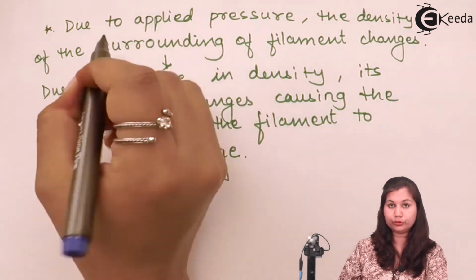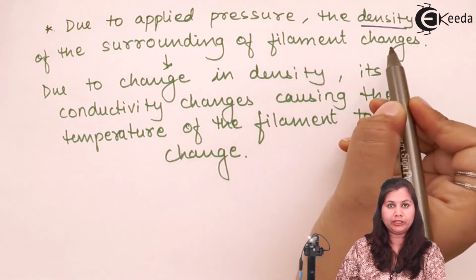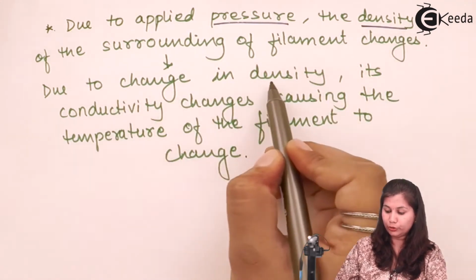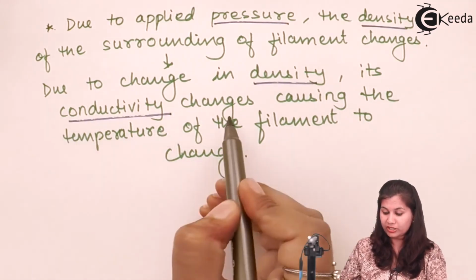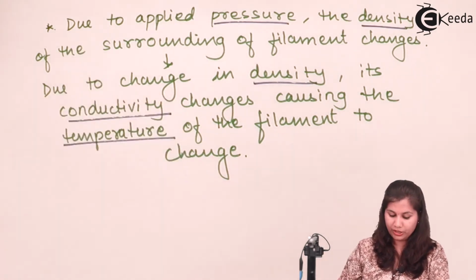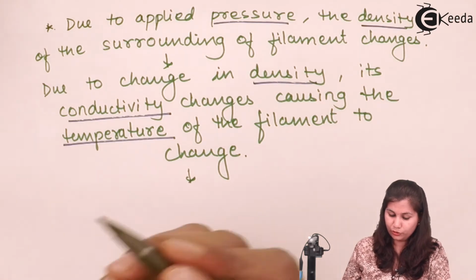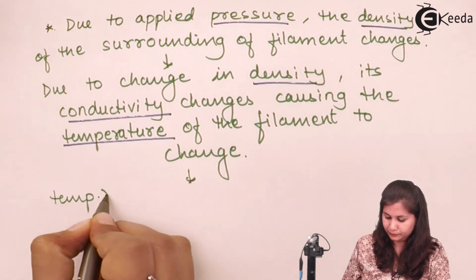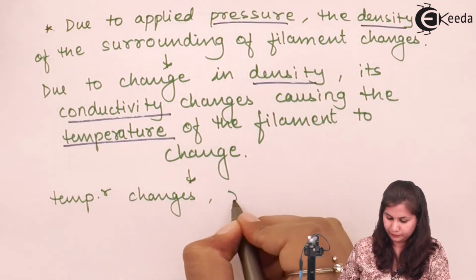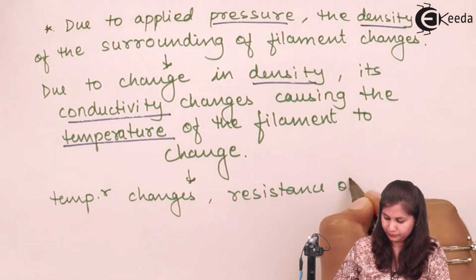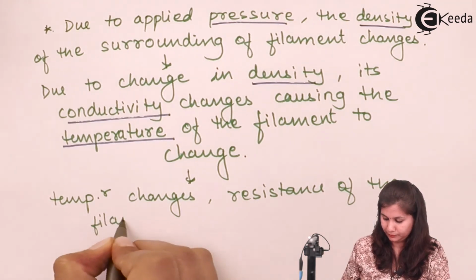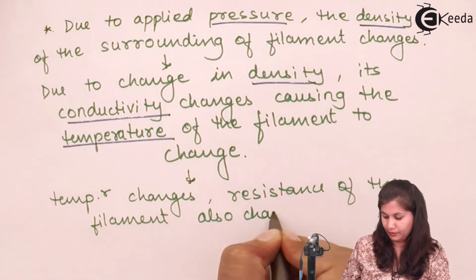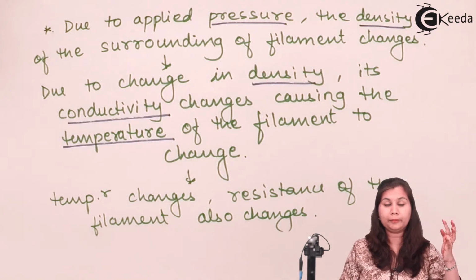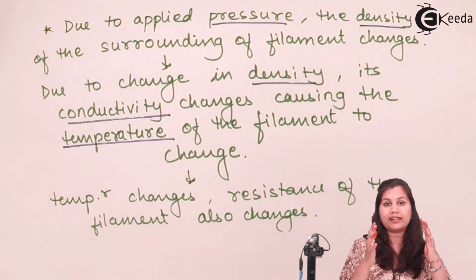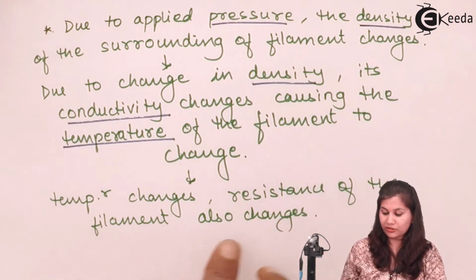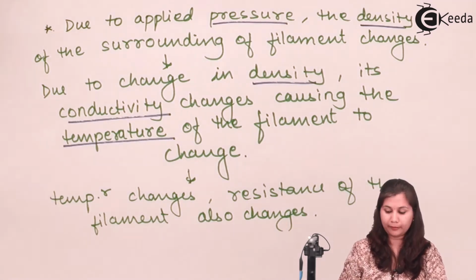So here you have seen that due to the applied pressure, the density of the surrounding of the filament changes. So due to pressure, density is changing, and due to change in density, the conductivity is changing. And due to change in conductivity, the temperature of the filament is going to change. And due to the change in the temperature, the resistance is also going to change. So you have seen how the pressure which we want to measure has affected the resistance of the filament.